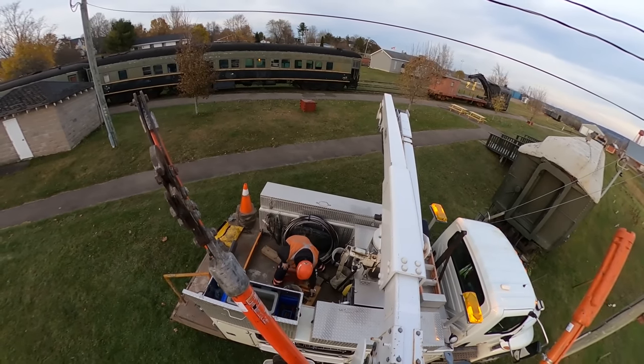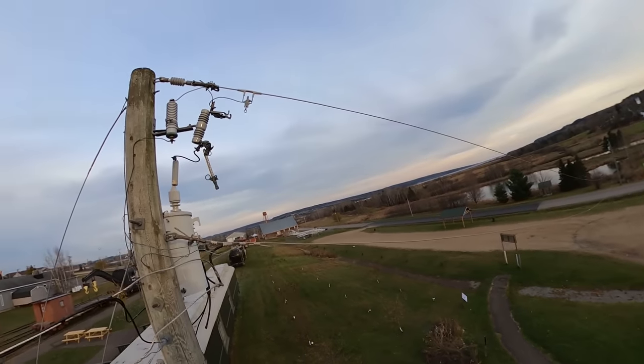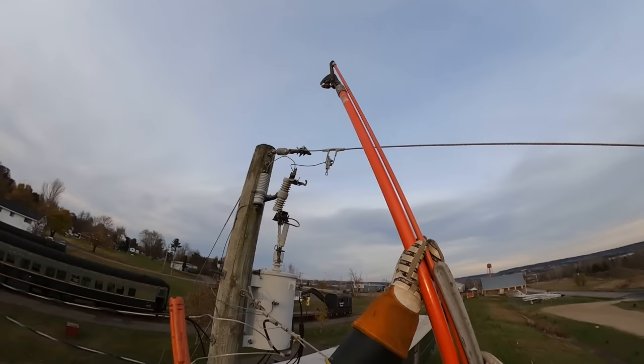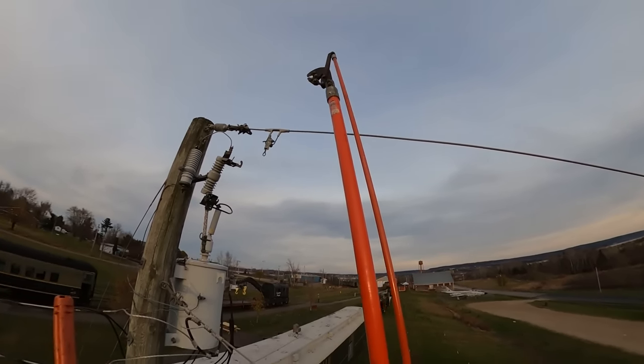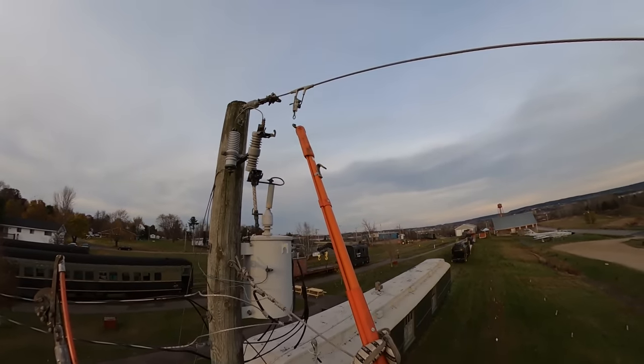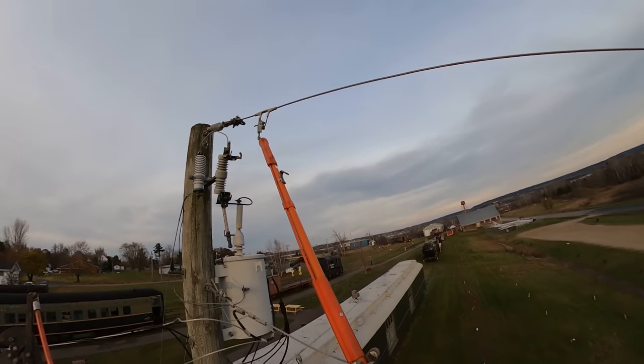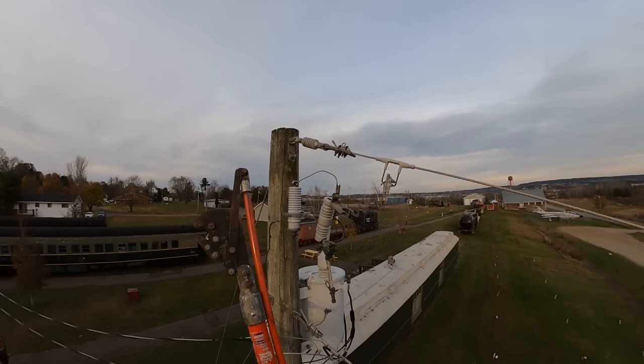I didn't have a lightning arrester on board. Nowadays the lightning arrester is always located on the transformer, so when you're tapping leads on you're not picking up that lightning arrester. But that's an older transformer and I don't have a lightning arrester on board, so we will change that cutout and get rid of that porcelain cutout. What we're doing here — we're using our tested six-foot bolt cutters and we'll cut that lead clean off. You can see how I grabbed that lead. With those cutters, for whatever reason, when you cut something if you hold the lever in place you can bring it right to you, removing it from the bucket.